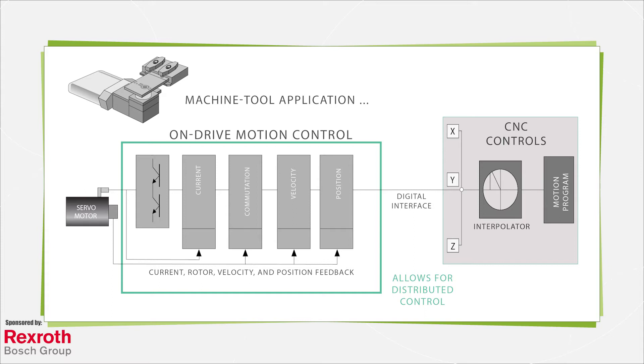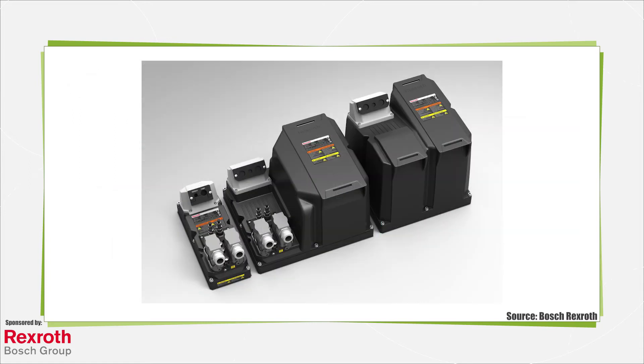These relatively new offerings underscore the appropriateness of the term amplifier used by some in industry to refer to drives, for the way they amplify low-power control signals into the full drive signals of electrical power supply. More specifically, drive-integrated controls from some manufacturers incorporate drive functions, motion control, and PLC logic on one open automation platform. Such IEC 61131 standards-based motion controls can execute complex motion tasks and even act as a master or slave in machines that need to coordinate motion axes in real time.